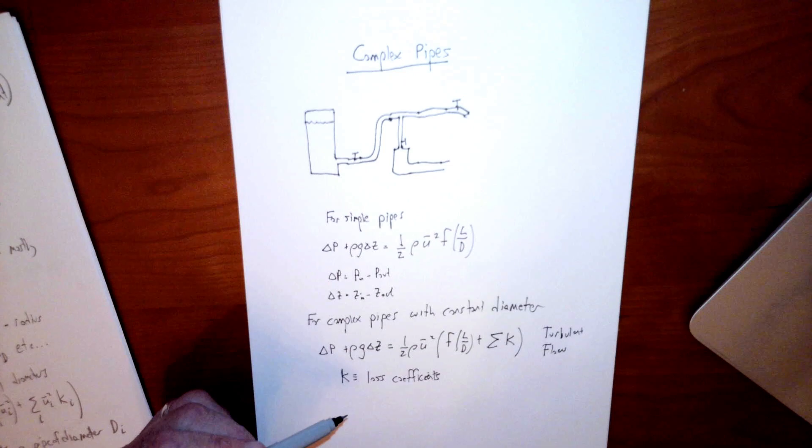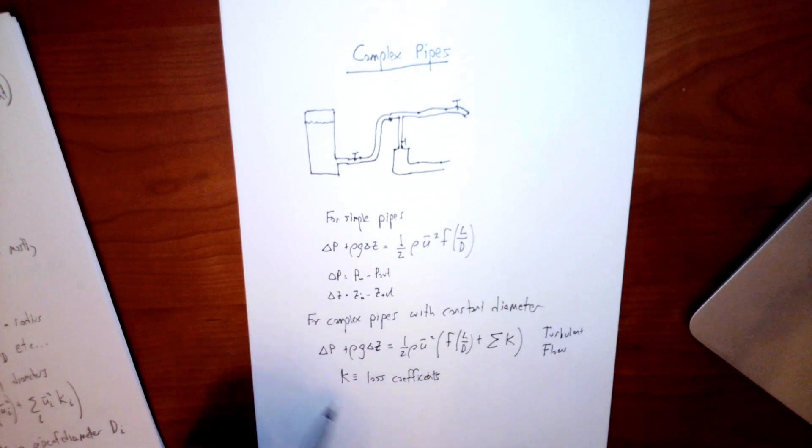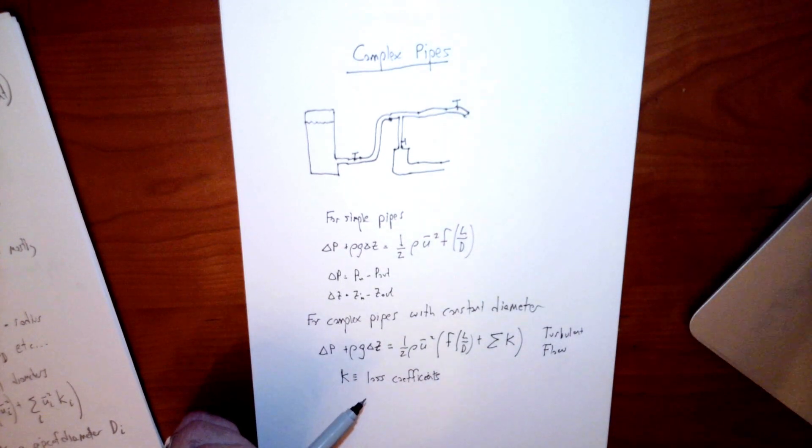They depend on, if it's a bend in the pipe, it depends on exactly how the pipe is bent. How much is it bent? How is it bent, slowly or sharply, the radius of curvature of the thing? What type of valve? All these things matter. So these K's, there are lots and lots of tables for these, and you have to be very careful to pick out the ones that are relevant to the problem you're dealing with.